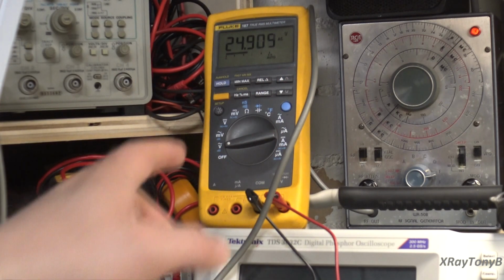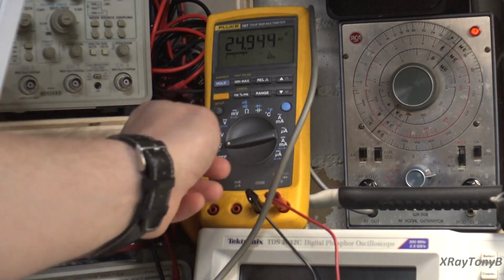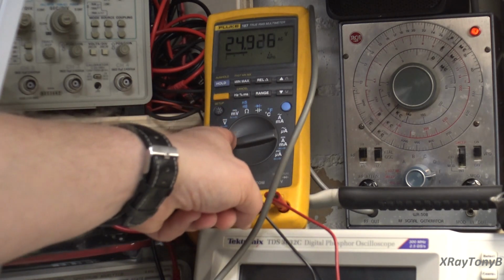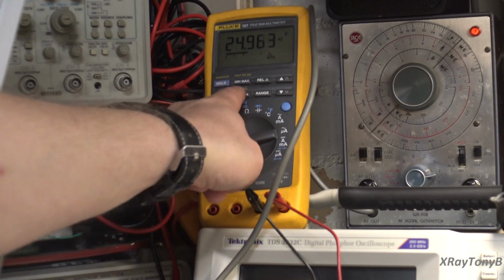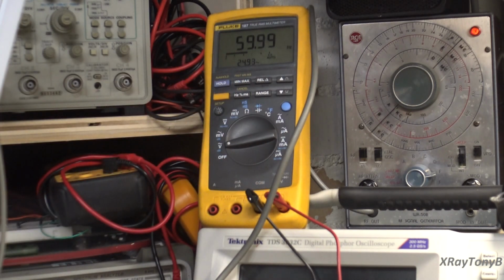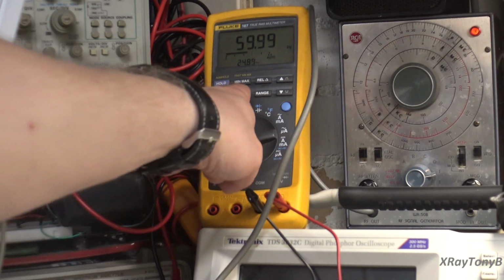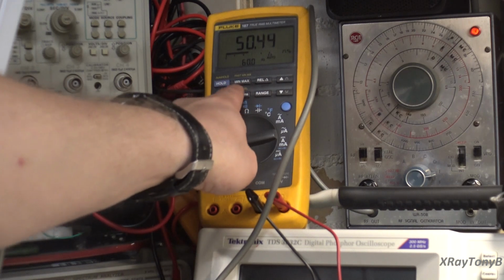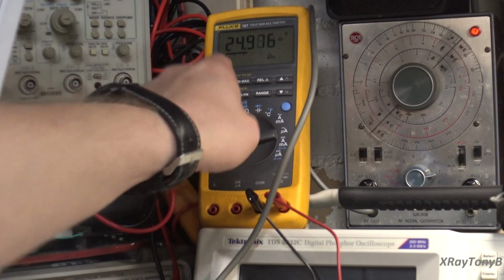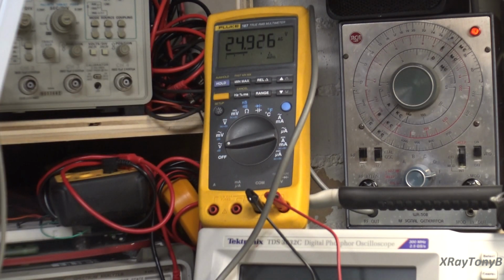If I look at the frequency, it's a 60 hertz noise, so it's line noise, because here in the States, our incoming mains voltage is at 60 cycles per second, or 60 hertz. So basically you have 25 volts of noise.